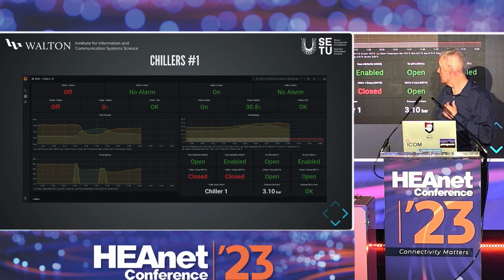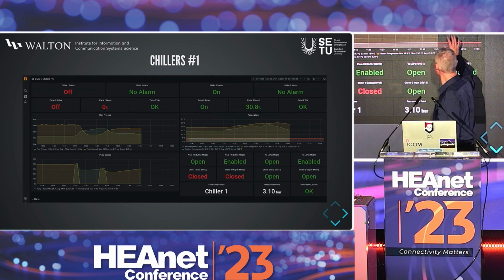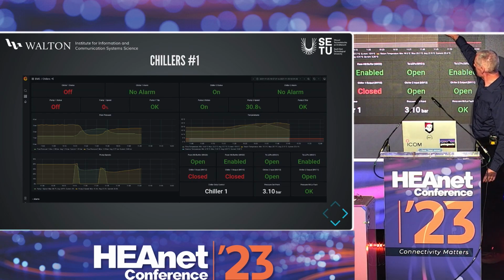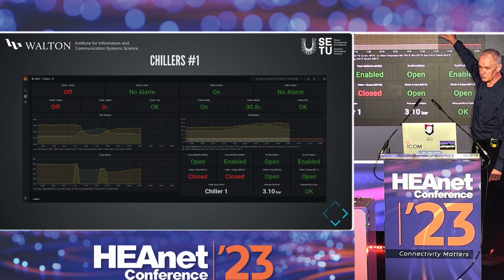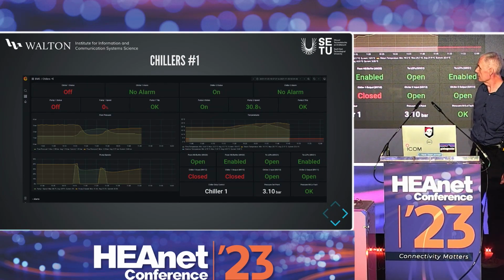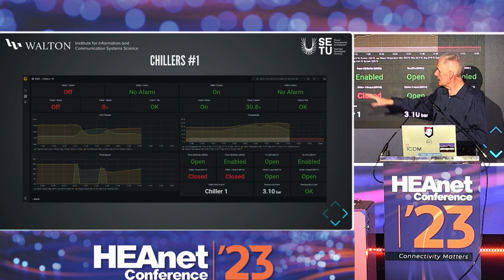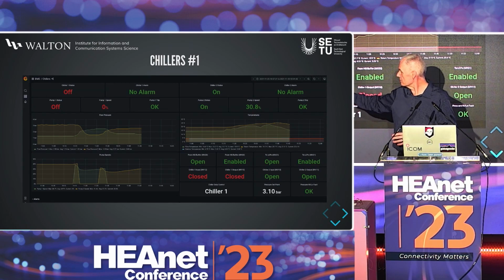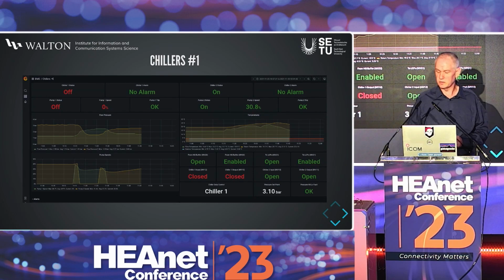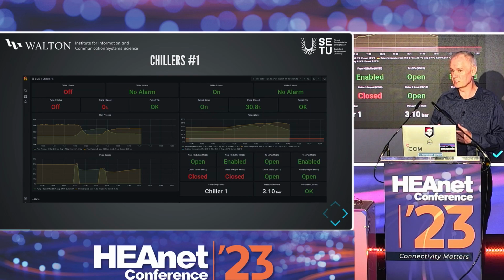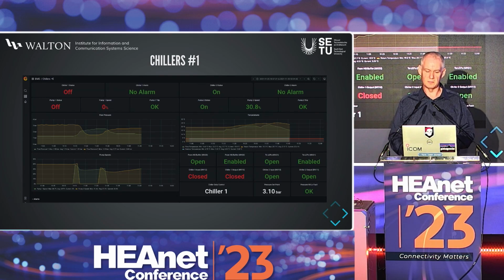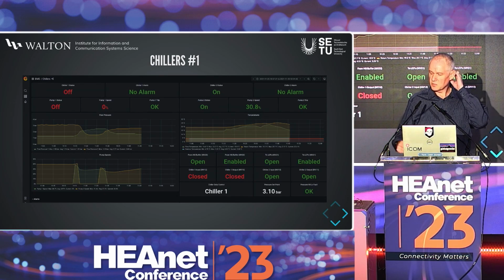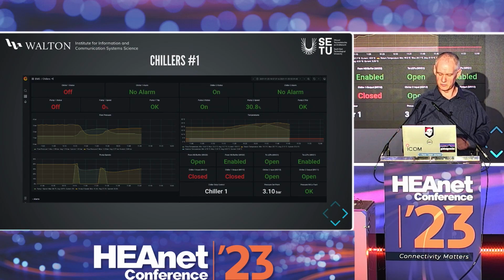The interesting thing here, and this is what confused me initially, is the system was actually recovering when the power tripped, when everything went. That was really confusing for a long time until we went back and looked at it. You can see the two chillers swapped over, and there's a fairly long gap between one and the next one. It's an active standby system. Generally, one drops off and the other comes in immediately. Temperatures were coming down, the system was recovering, and the power still went. We still went through the maximum load, and that was confusing.